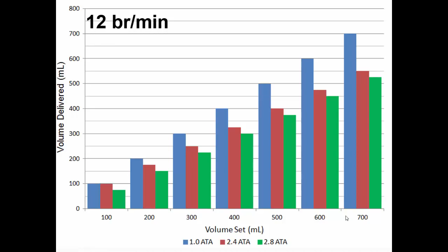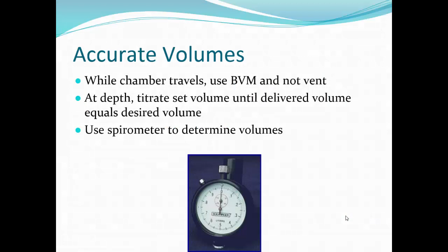And when you're managing these vented patients with volume cycle ventilation, typically we take them off the ventilator on travel, so going in descent and ascent, and you bag them on the way down. And then at depth, you try and set the volumes, and you have to actually measure the volumes. Here's a little spirometer. The vent will deliver a breath, and you'll see what kind of breath comes out through the spirometer, and that will tell you it's actually 300 versus 400 while at depth. But even these spirometers are not perfect.